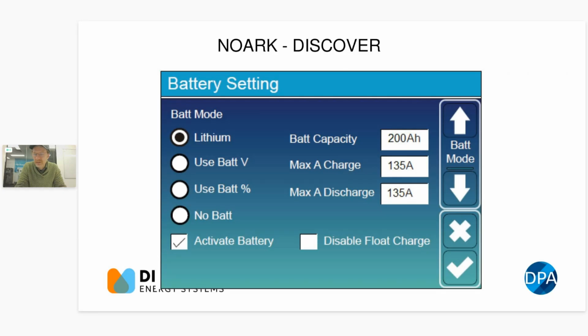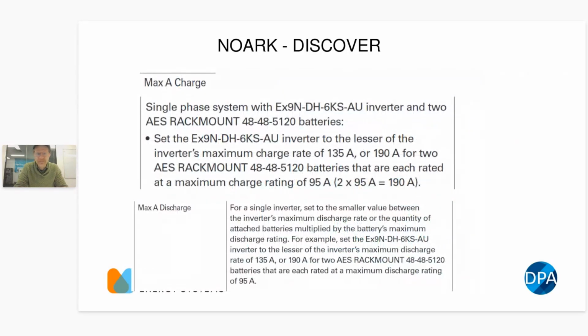Obviously, it's going to be set to lithium if you're doing closed loop with Noark. And then you're going to have to set the maximum charge ratings and the battery capacity. You have the maximum charge settings here, and you have the maximum charge that you're going to receive over the CAN bus, and the inverter is always going to use the lowest value, right? So if the battery is saying you can charge me at 100 amps, but you set a maximum charge rate of 80 amps in here, then it's going to go 80. Whereas if you set the maximum charge rate in here as being 100, but the battery's saying only give me 50, then it will only do 50. It'll always take the lowest value. And the same with the voltages and things like that.